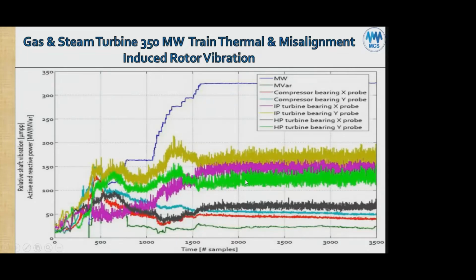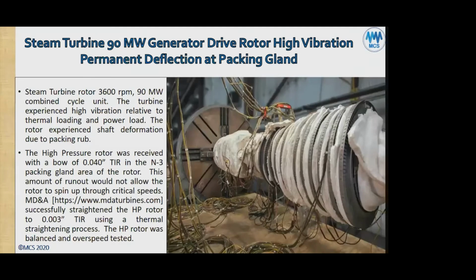Okay. We're going to get down to the machines now, closer. One more example of sources of vibration. Here we have a 90 megawatt steam turbine rotor. It's a combined HP and IP, and it looks like LP also. It's a single casing, 90 megawatt combined cycle steam turbine. The turbine experienced high vibration relative to thermal loading and power load, so shaft power load and thermal load, both.